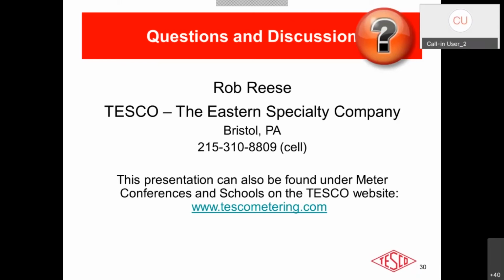Step 2 would be on say a 9S installation where you have a bank of 3 CTs and they're all the same ratio, same model, same manufacturer. They should all have very similar millisiemens values from an admittance test. So if you test each of the CTs in that bank and you get, say, values of 10, 10.2, and 18, the CT that gave you the value of 18, that's an indicator that something's wrong in that phase. And then lastly, the 3rd step is to test over time.